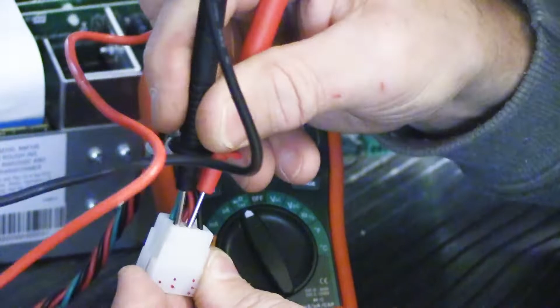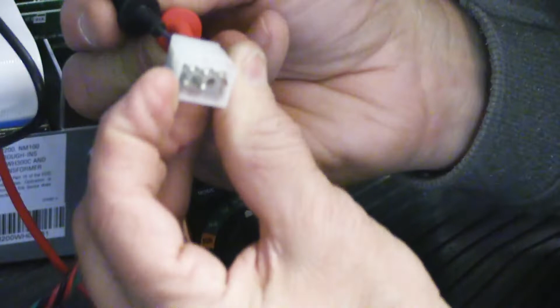Now you notice I'm measuring on the back side where the wires go in, because you can see the metal that's crimped onto the ends of the wire. You can also do it inside on the pins if you want to. You just have to make sure the probe leads don't cross over the pins, or you'll get a false reading.